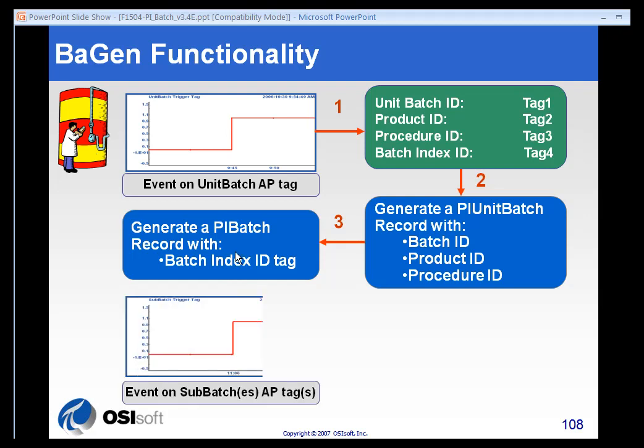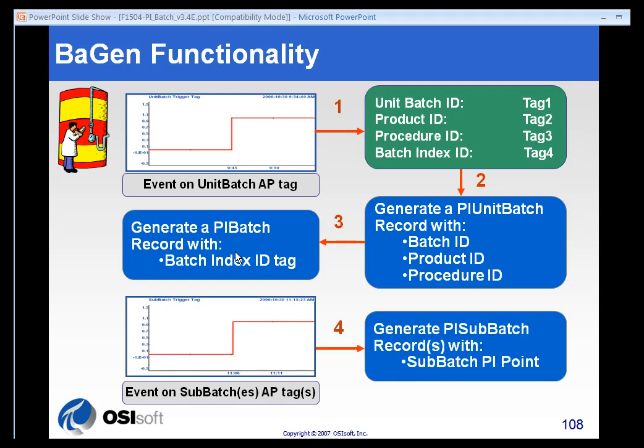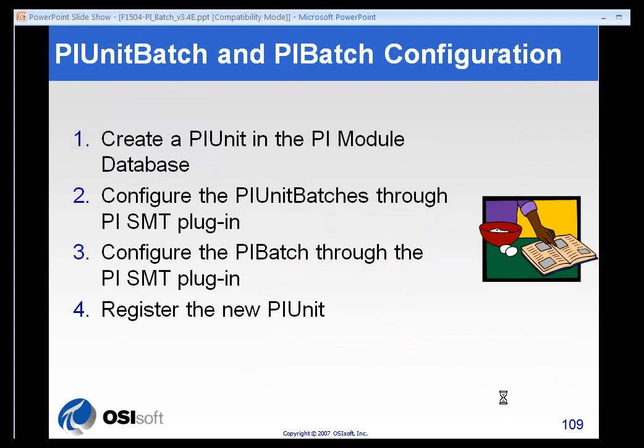Optionally, if there are sub-batches, their active trigger tags are monitored. If those change state, we will generate a sub-batch record using the sub-batch PI point active point, and we'll create start and end times for the sub-batches as well.